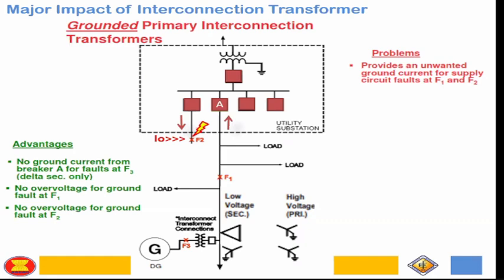Or else you will implement a directional relay to simplify the coordination. But the problem is that the DG has to invest, as we are the distribution owner, responsible especially the distribution engineers, in charge of protecting our system. We require the DG to invest in that protection, the directional, because it has an impact. If we do not address that, it may cause miscoordination, impacting customers on this line, so you have a widespread brownout or blackout. So those are the problems with the grounded primary.